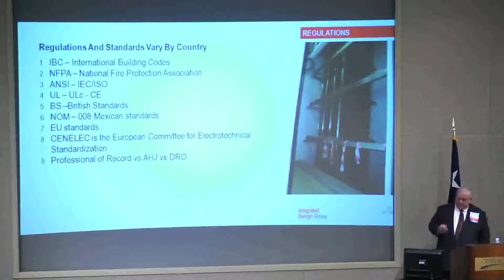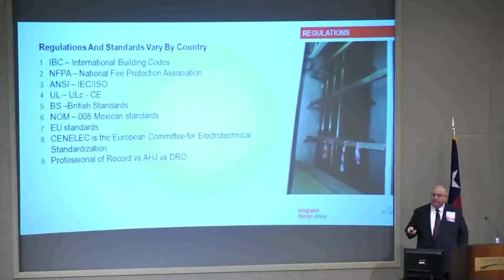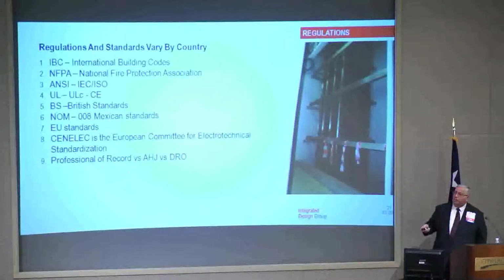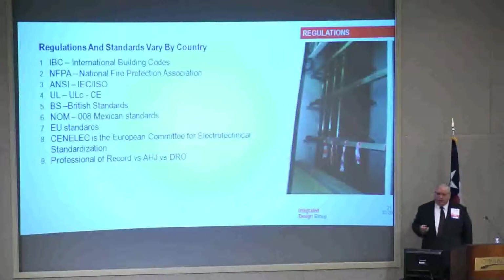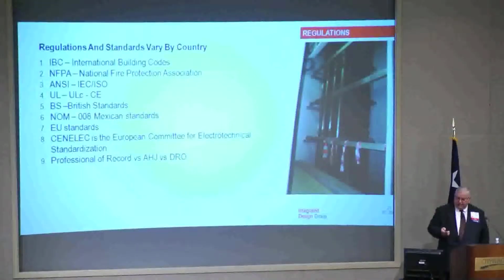What we show on the right is a picture with some cable tray with conductors in it, as was mentioned earlier. That's a very common design in other countries. That's a British standard requirement. They don't use conduit very often. Whereas in NFPA 70, which is the National Electrical Code, we tend to use conduit all over the place. So it really makes a difference in your designs and how you approach them, depending on what standards they're going to follow.